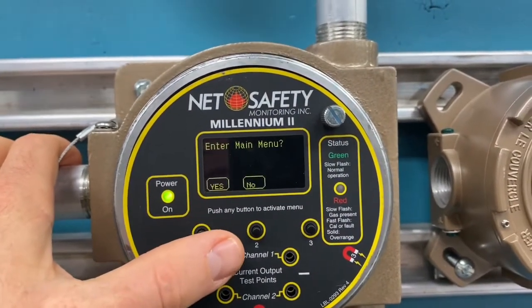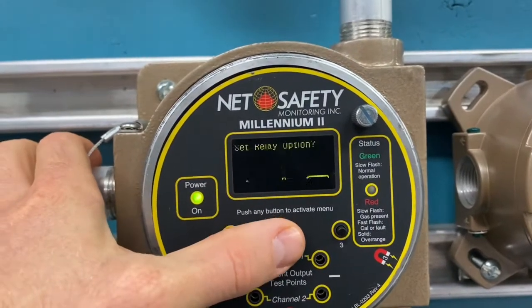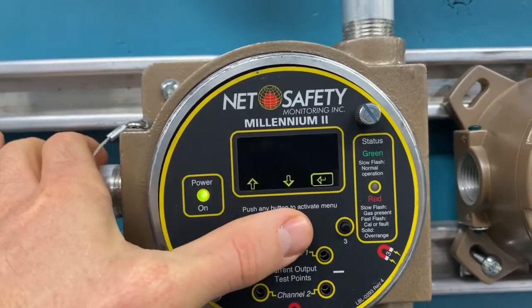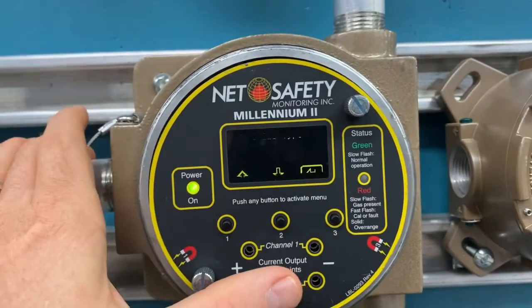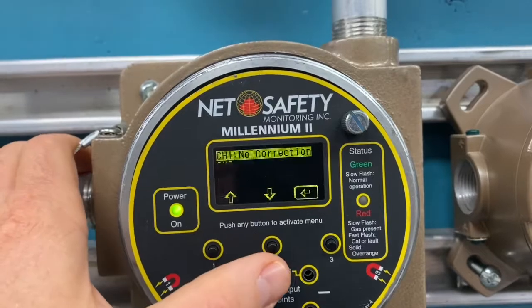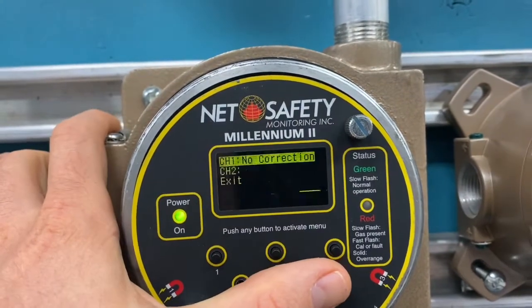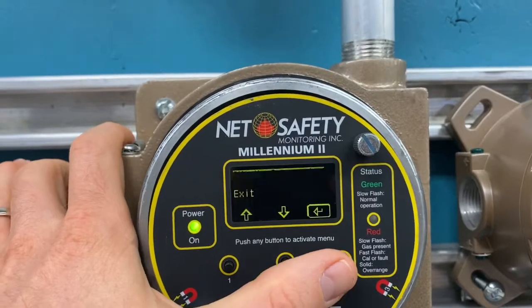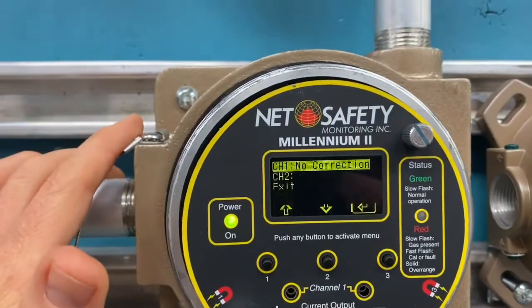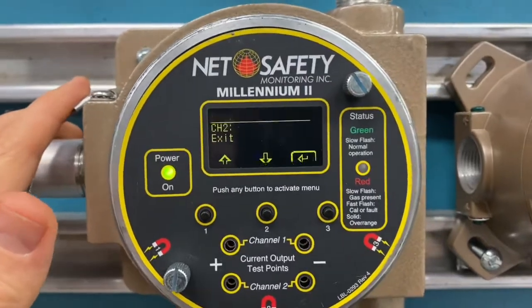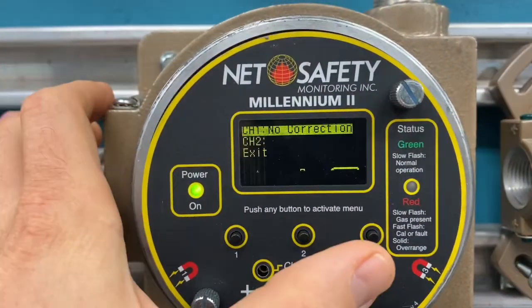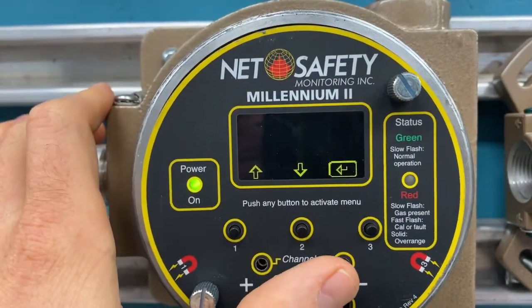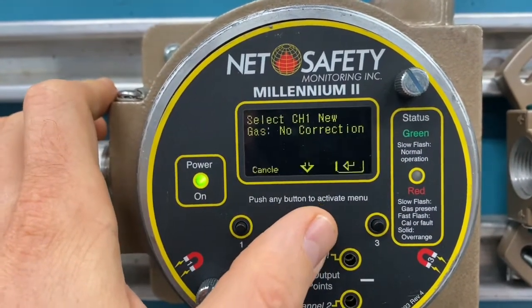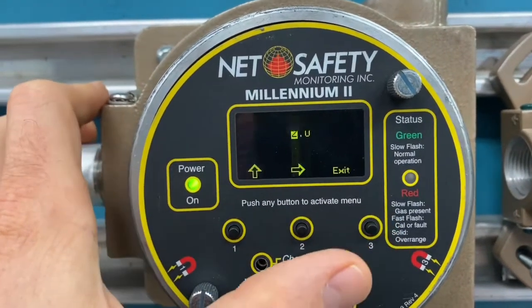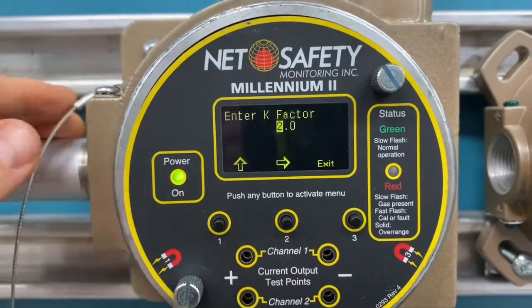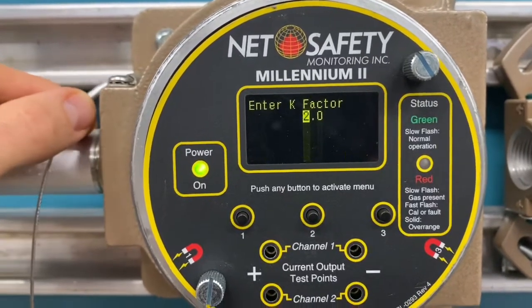Okay, so one other thing that I'm going to have you look up in the manuals is a value here. We're going into the main menu, and if we go down to select gas type, so under select gas type here, we're on channel 1. There's no correction being applied right now, but in the manual there's a table that tells us the correction factor to use. If the only calibration gas you have is methane gas like we have, we can actually calibrate this for other gases like propane or hydrogen or things like that. And so if we go into there, you can see that we can toggle this to a custom correction factor, and then we can change that value right there. So what I'm going to get you to do is to look up the value for hydrogen, and we're going to answer that in this lab.